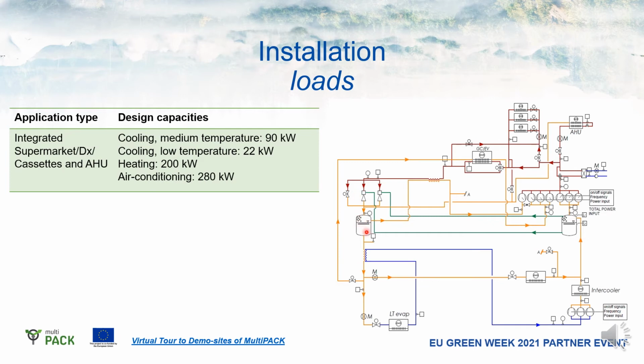In the separator, the vapor and liquid are separated, while the vapor part is taken care of by the parallel compressors or the flash gas bypass valve. But mainly the parallel compressors maintain this pressure level. The liquid is provided to all the evaporators, and in case of a heat pump function, additionally the liquid is supplied to the outdoor heat exchanger, which can operate as an evaporator, while the vapor is taken back to a special compressor suction part to enable the heat pump function.